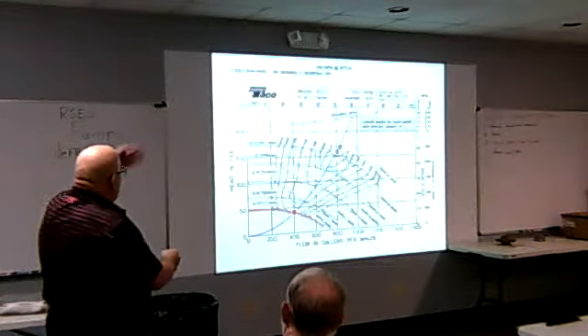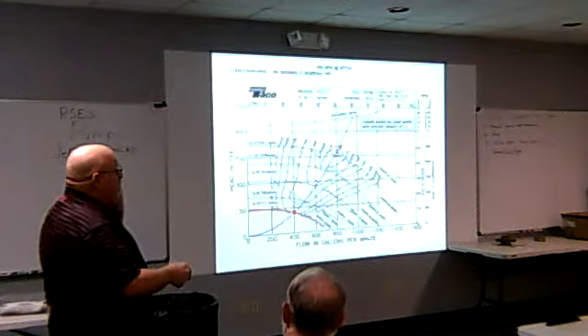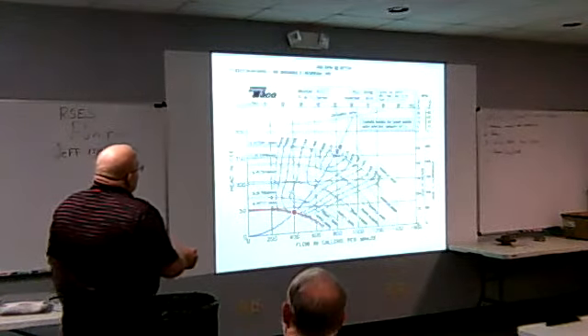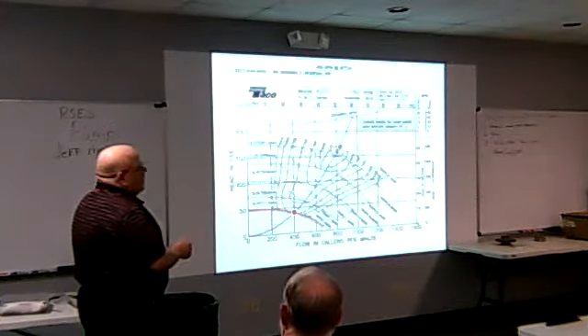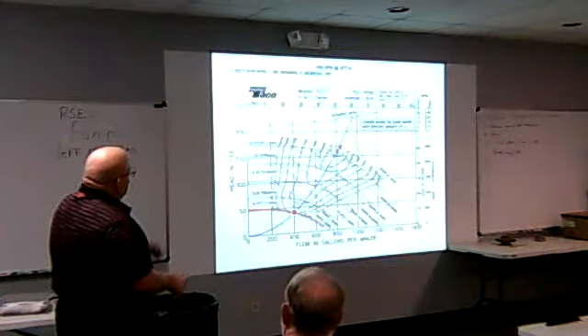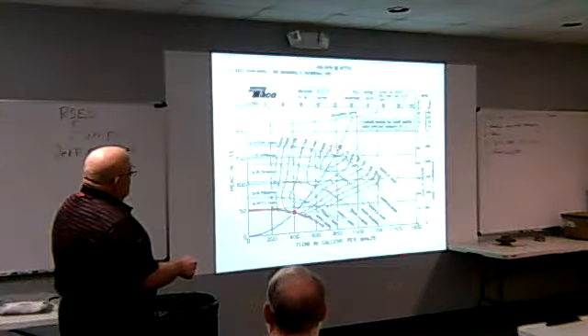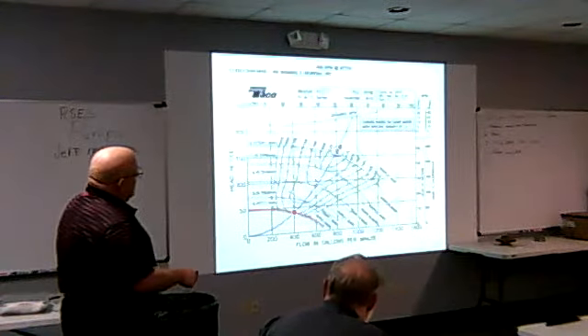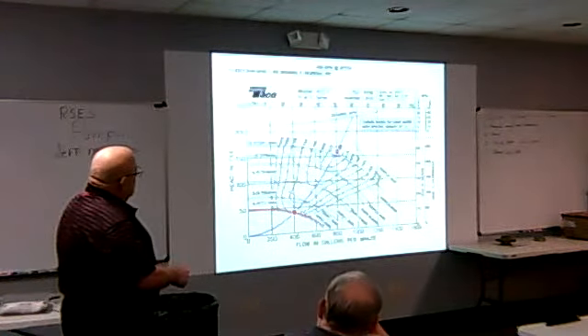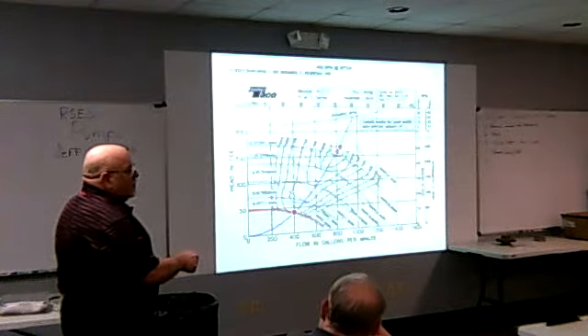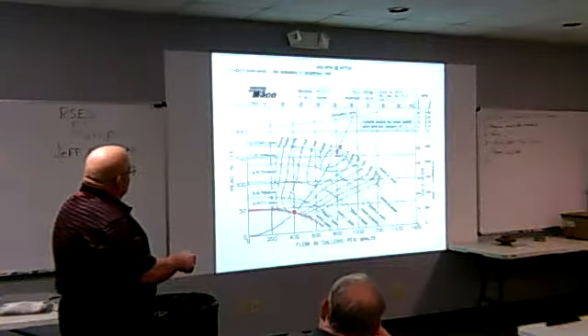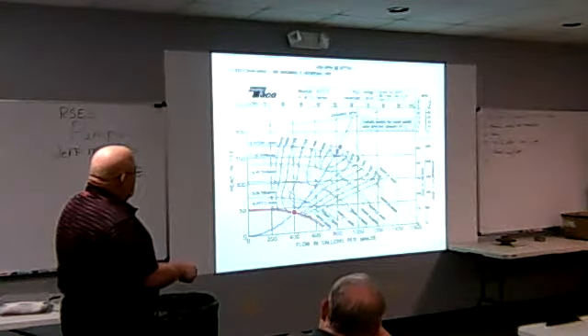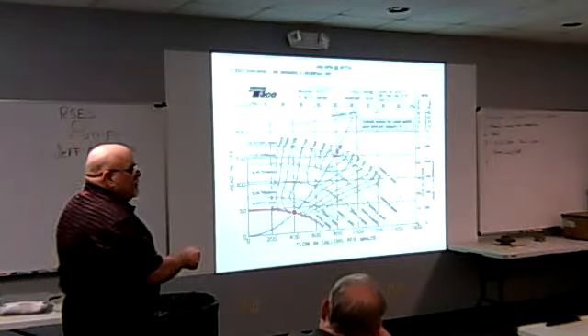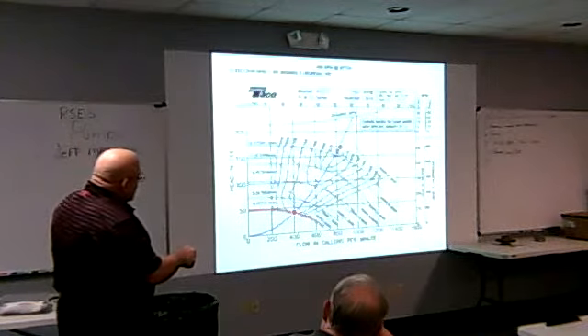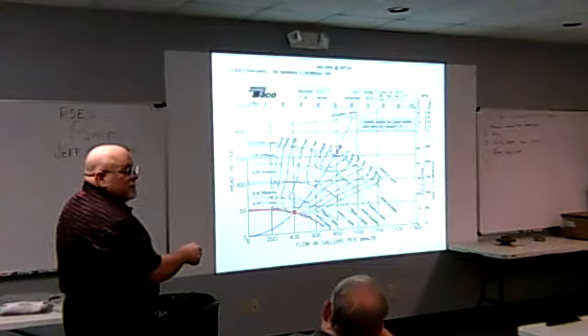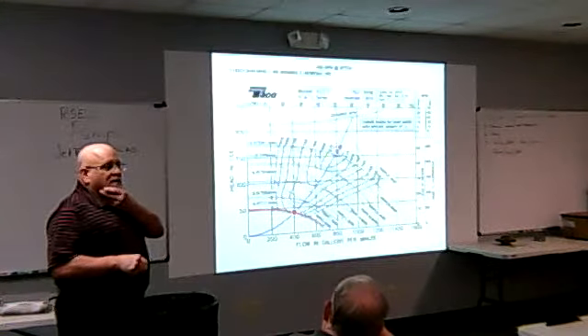Let's say we need more horsepower, we need more flow. We want to evaluate this pump. When I come in here at 440, I use my affinity laws. I say, okay, we want to go out to 800 GPM. Well, if I put a 12.75 inch impeller with a 50 horse motor, it might do it. But from where I am here, this is a true point. This pump's no good for that. I'm only going to get 800 at 150 feet. I can't get 800 GPM out of this. This is the most flow I'd ever get. If I change it to a max impeller and put a big motor on it, this is the best I can do. I can't get there from here with this pump. I have to change the pump. Are you following that? Make sense?